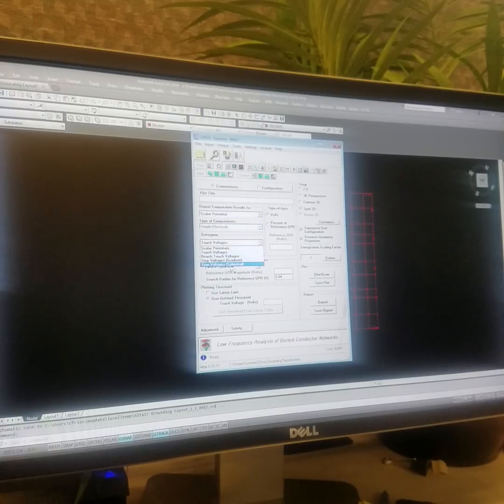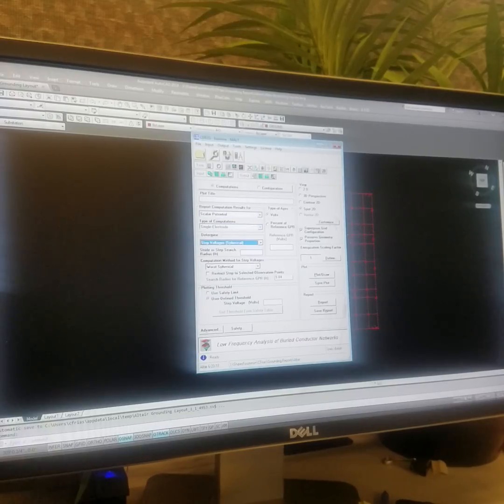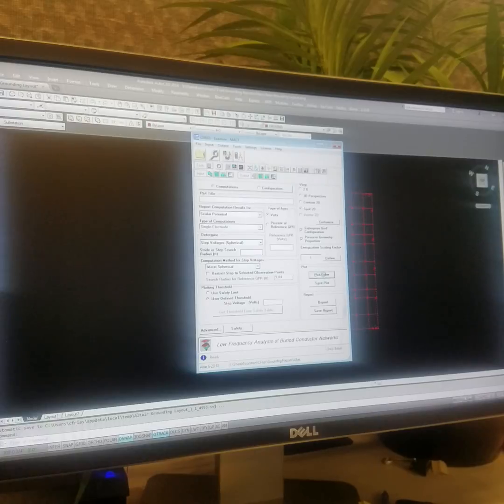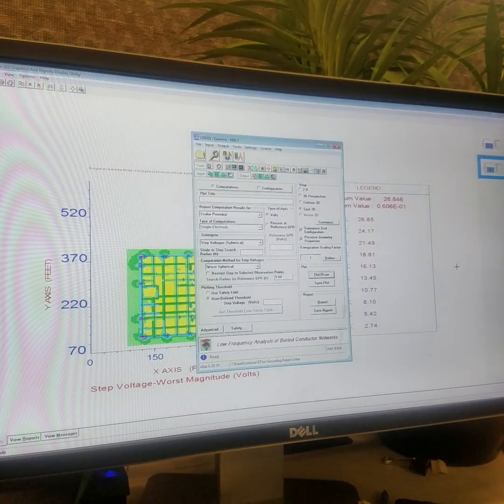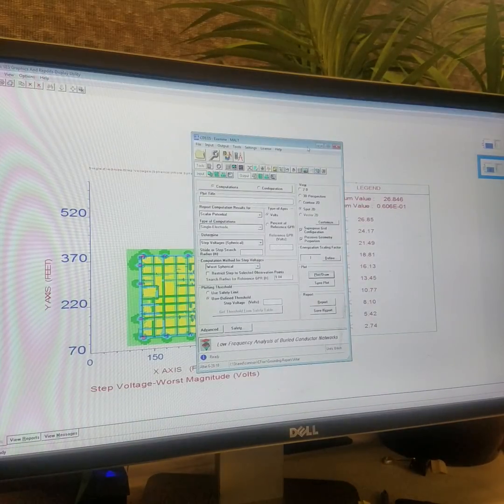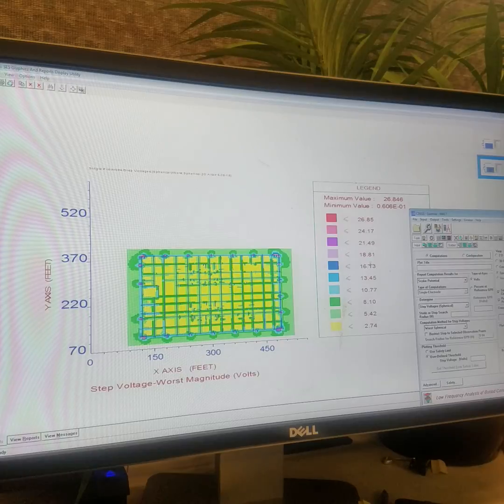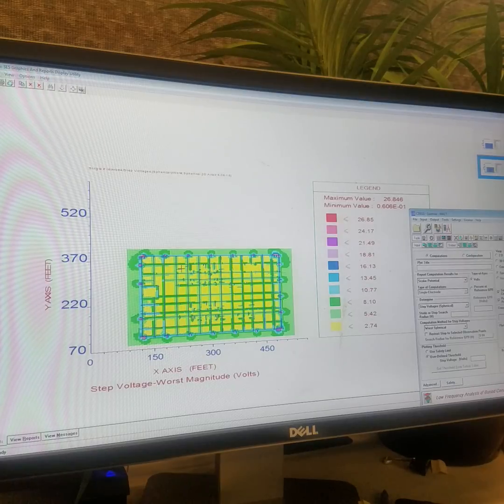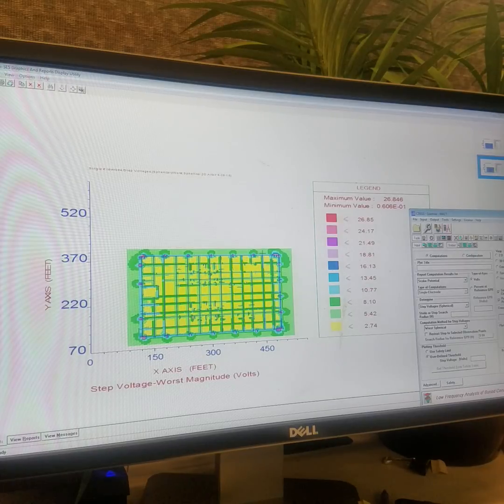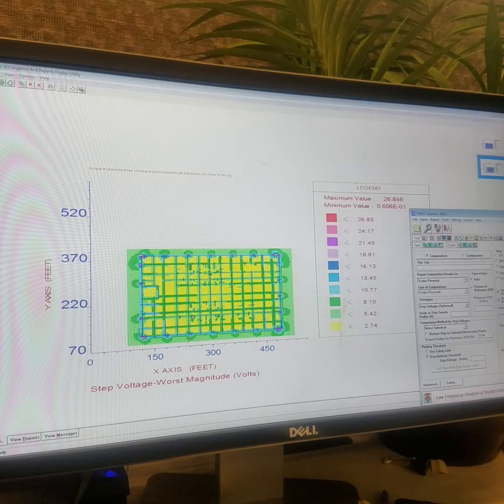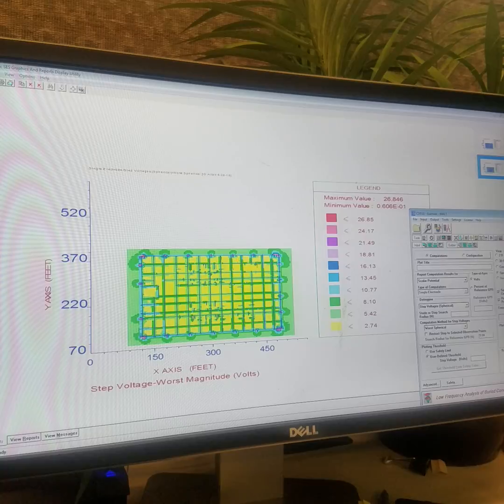Click down here, this one, hold up, which one is it? Yeah, step voltage spherical, click plot and draw. I think it's out of the way. So those are our ground rods, they really help, you know, bring everything down, and everything is really small voltage values.